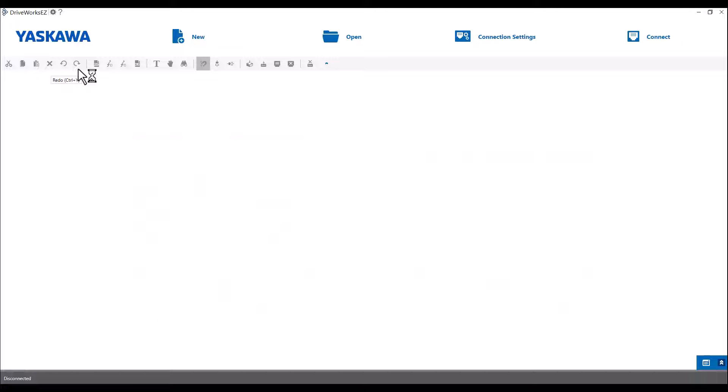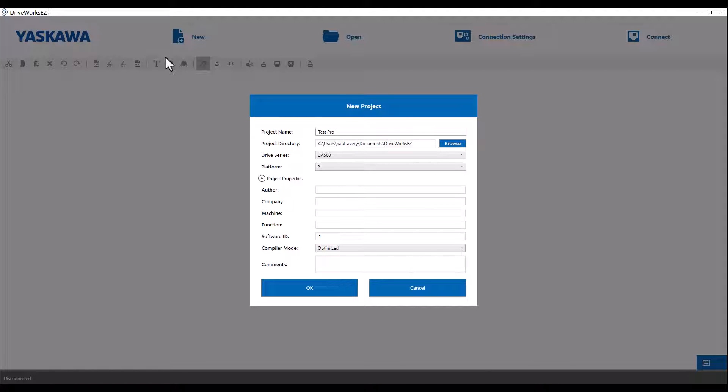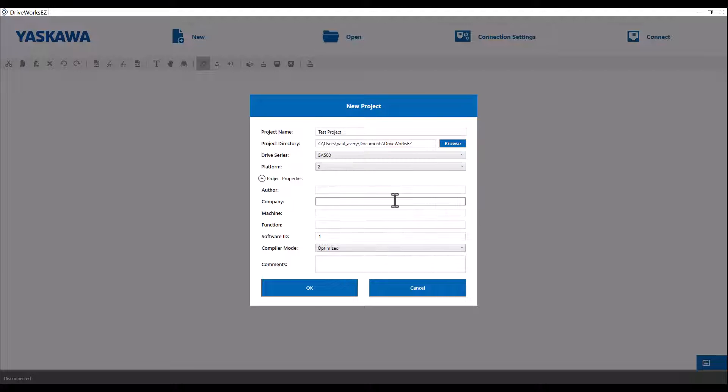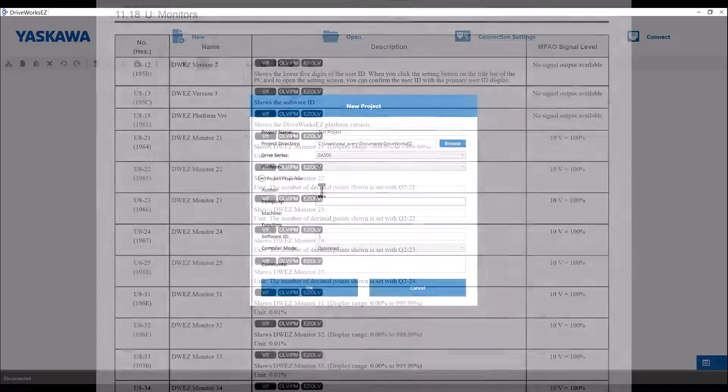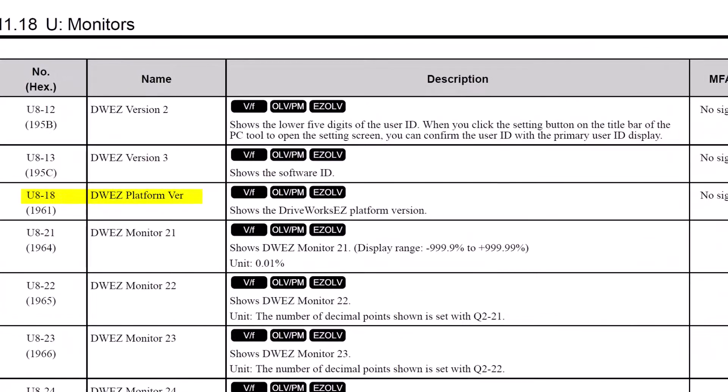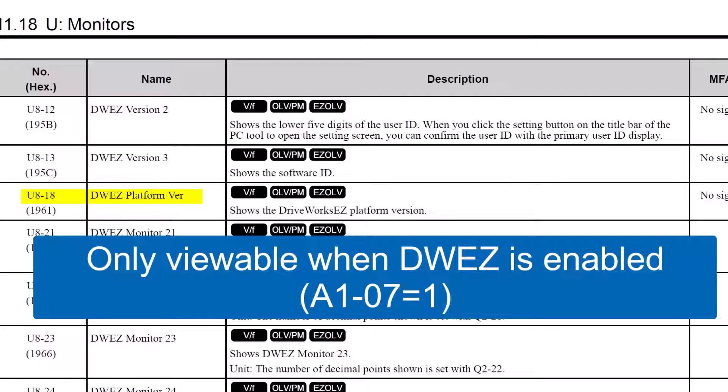First thing we must do is start a new project. Simply click the new icon and start a new project. I am going to name this Test Project. Use your dropdown selections to pick out your drive series and your platform, which can be found using monitor U818 of the drive you are connecting to. If you can't view the U8 monitors, make sure that A107 has DriveWorks EZ enabled.